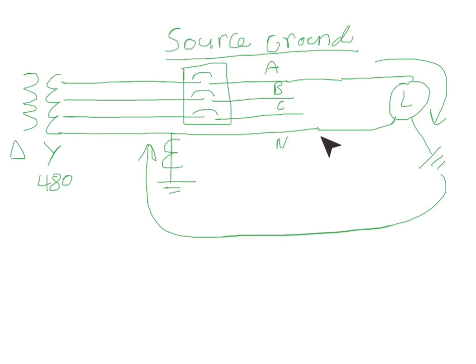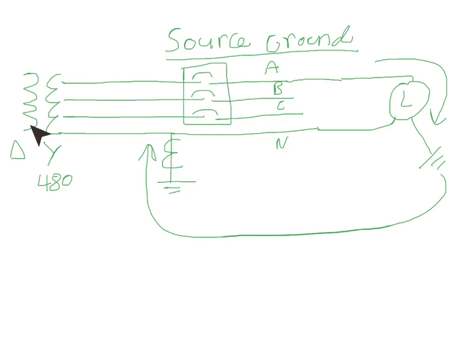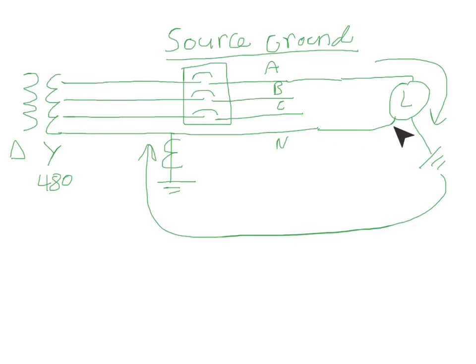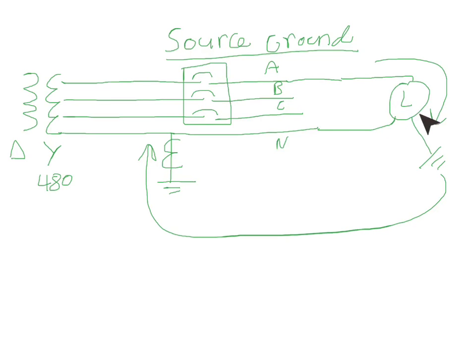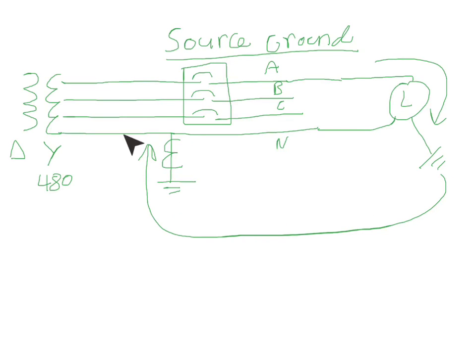It doesn't go down to ground, it goes back to the source. So that's how it would return. Same thing with a three-phase load - you have a three-phase load, there would be no current returning back on the neutral for a three-phase load. But if there was a fault, it would return to ground and it would come up on this ground bar here and go back to the transformer.